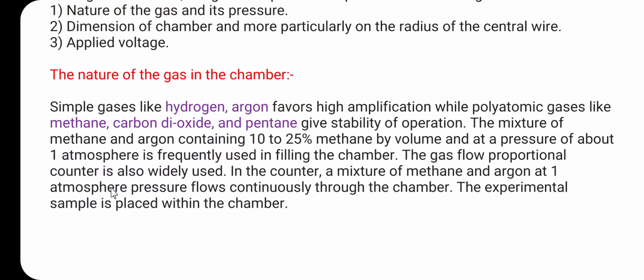Now, the nature of the gas in the chamber. Simple gases like hydrogen and argon favor high amplification, while polyatomic gases like methane, carbon dioxide and pentane give stability of operation. A mixture of methane and argon containing 10 to 25% methane by volume, at a pressure of about 1 atmosphere, is frequently used in filling the chamber.